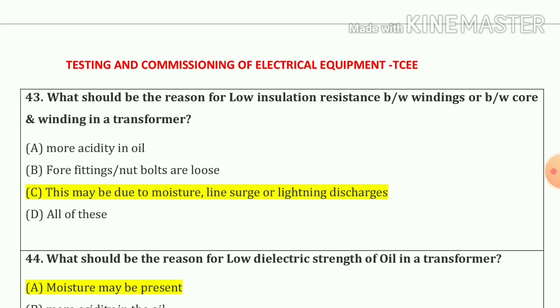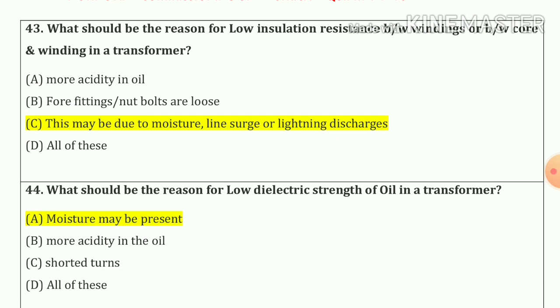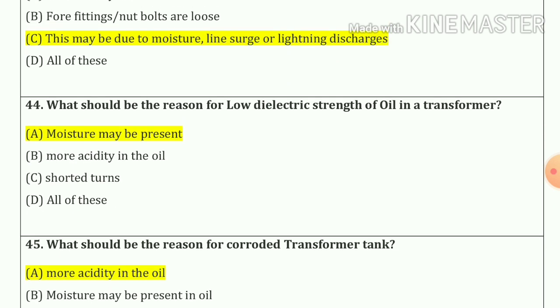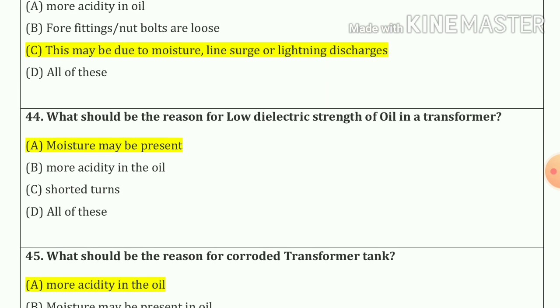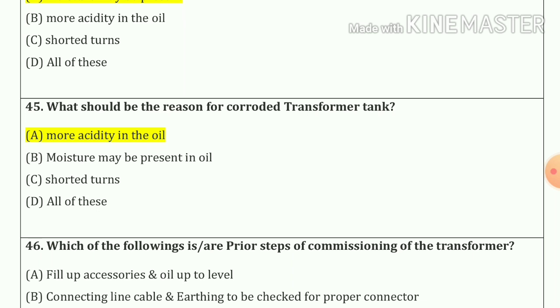Now question number 43. What should be the reasons for low insulation resistance between windings or between core and winding into the transformer? So our answer is option number C. This may be due to the moisture, line surge or lightning discharges. Now question number 44. What should be the reasons for low dielectric strength of oil into the transformer? So our answer is moisture may be present. Question number 45. What should be the reasons for corroded transformer tank? So our answer is option number A. More acidity into the oil.